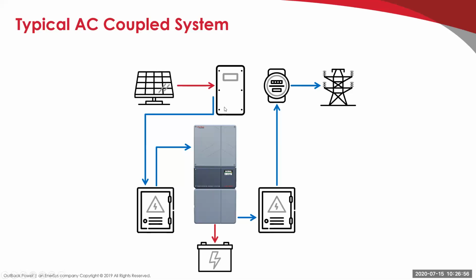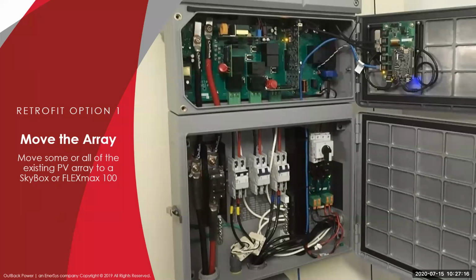So when we're grid connected, it's just self-consuming. Whatever energy is produced on the backup loads panel goes to the inverter. It gets self-consumed here. If there's anything left over, then it goes on out to the grid. No different than normal operation than what the grid dependent inverter was doing before. Okay?